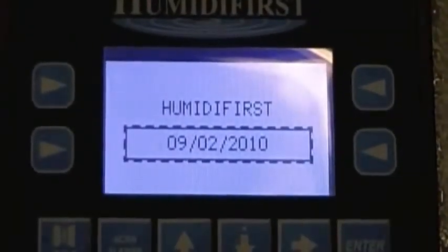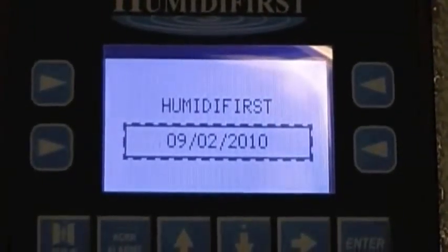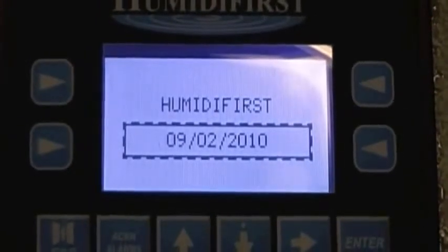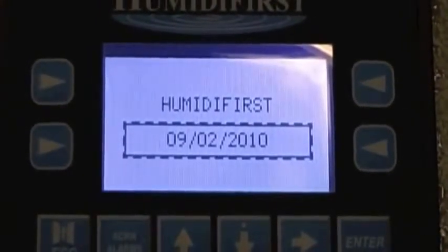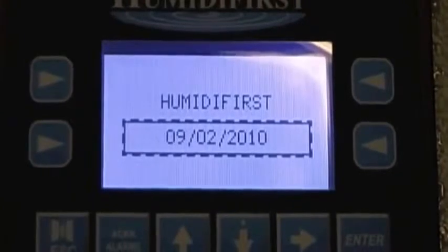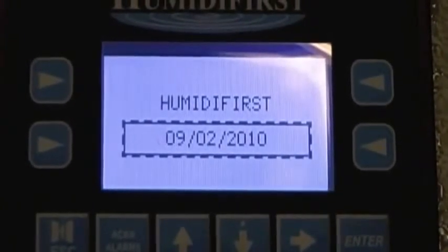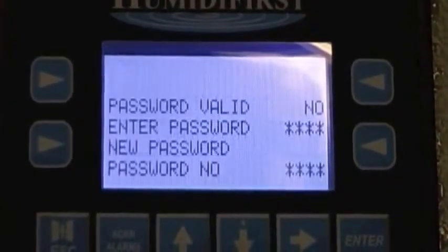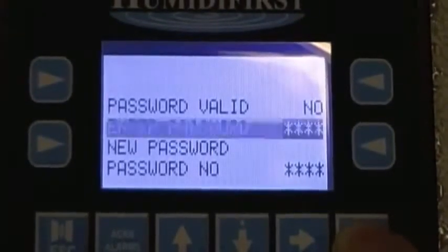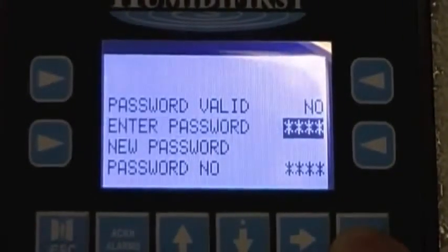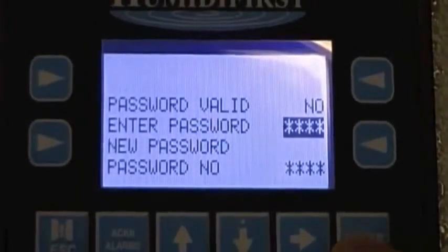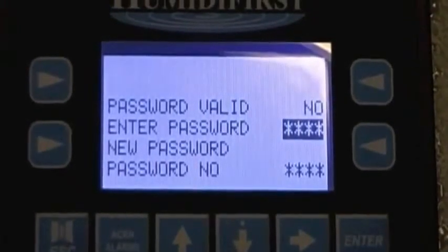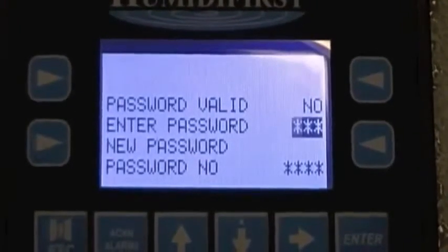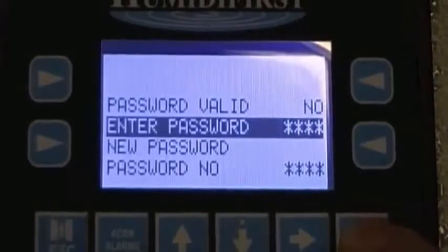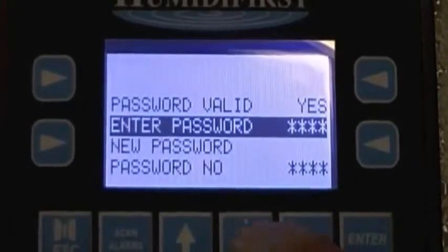We will now go over button number 1, change password. Your system comes with a factory password of 4444. To change this to a password of your choice, you would press button number 1. You hit enter to enter the menu, and enter again until only your asterisks are highlighted. You put in the factory password of 4444 and press enter. Your password valid will say yes.